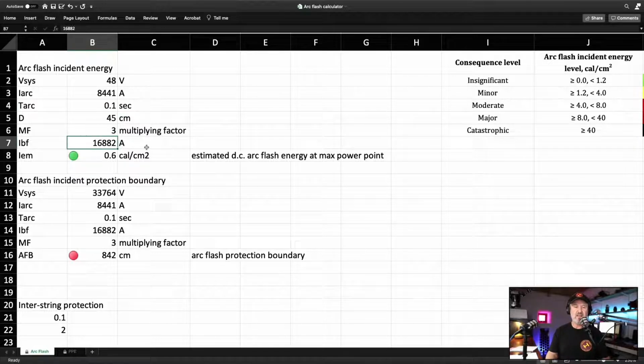So if I plug in here, double 16.8, so it's 33.6 roughly, 33650 roughly. And even though with 2 strings I'm up to 33650, I've really significantly reduced the arc flash incident energy, but it's still got quite a high arc flash boundary. So that means you really still need to wear PPE, but the level of PPE is very, very low.